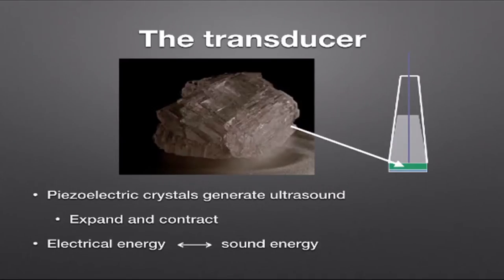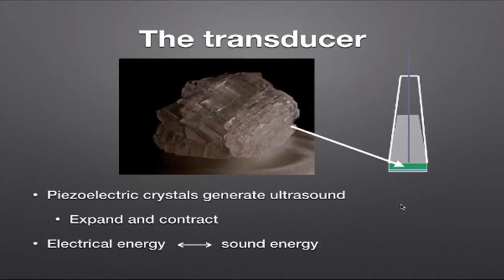The most important component of the transducer is the piezoelectric crystals, which sit at the top of the probe. By providing an electrical voltage to these crystals, they expand and contract, forming the ultrasound wave. Sound waves reflected off body structures return to hit the piezoelectric crystal, forcing it to contract and expand, transferring that energy back into electrical energy. These crystals are the foundation of ultrasound imaging — converting electrical energy into sound and sound back into electrical energy.